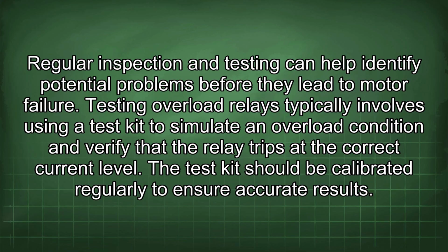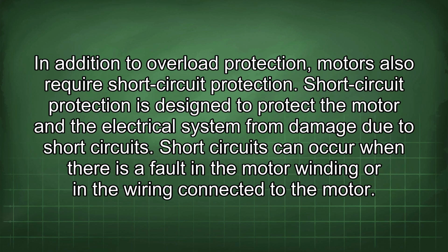Testing overload relays typically involves using a test kit to simulate an overload condition and verify that the relay trips at the correct current level. The test kit should be calibrated regularly to ensure accurate results. In addition to overload protection, motors also require short-circuit protection.